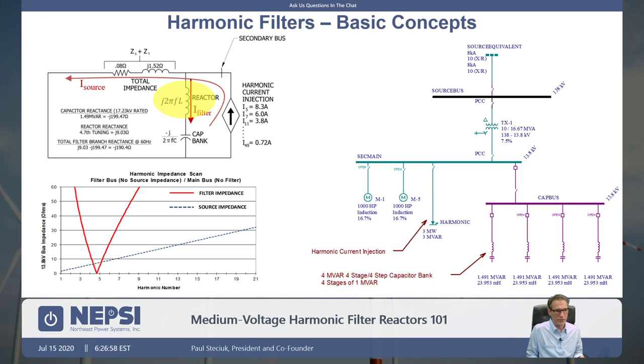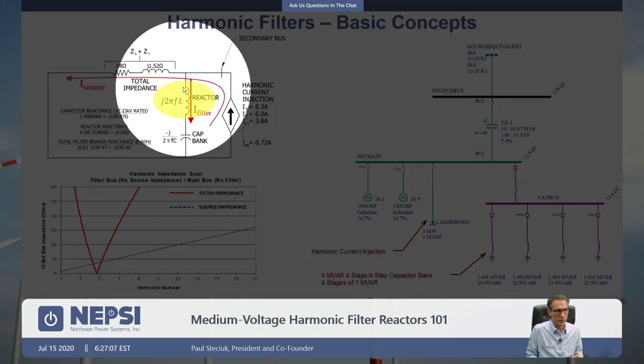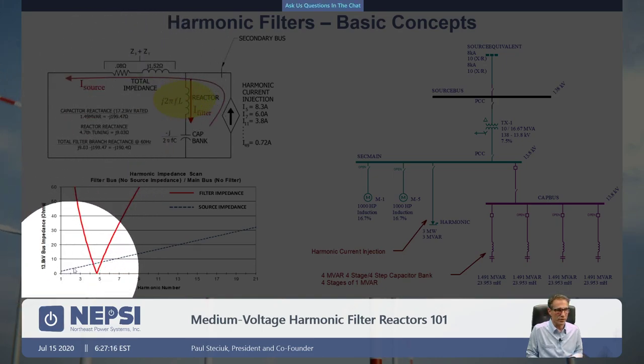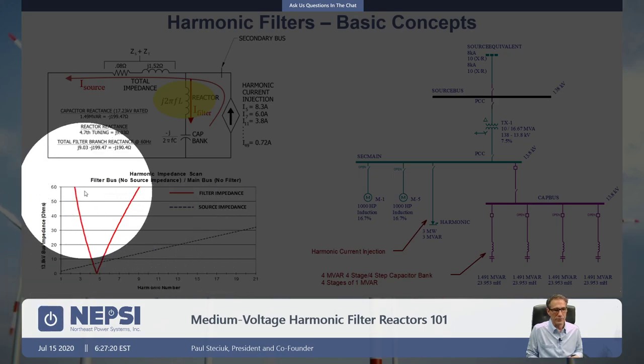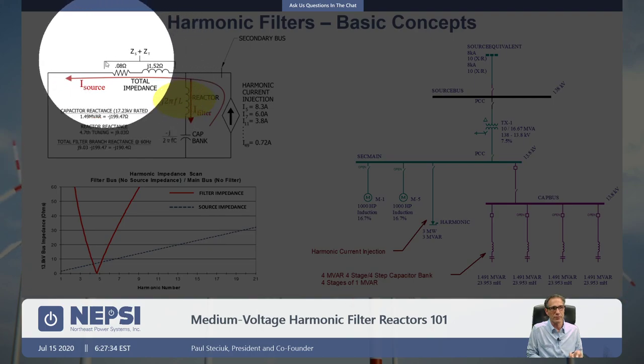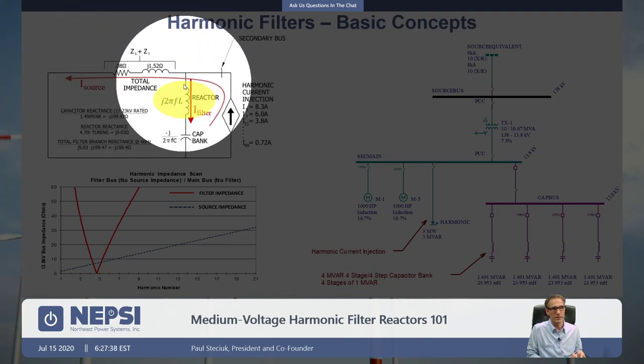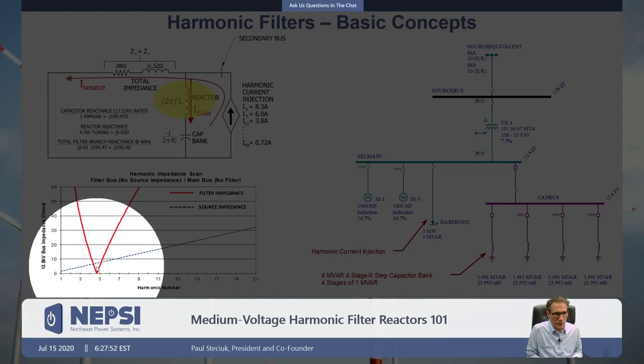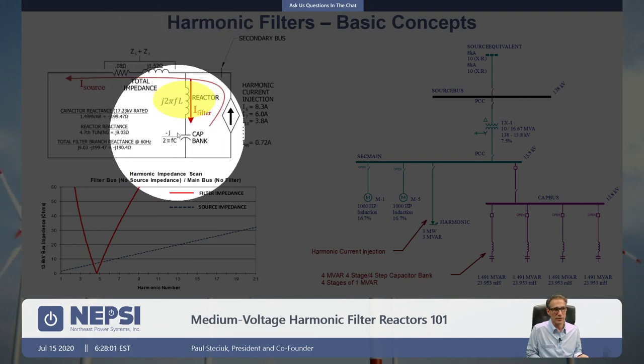Zooming in to the harmonic impedance plot, you see the impedance curve for the harmonic filter. We're looking at the impedance down into the capacitor bank — which includes the reactor and the capacitor — versus the impedance of the source, which is a straight line. When you install a filter on a system, the filter will take harmonic current from the source based upon an impedance current divider between the source/transformer impedance and the filter impedance. At the fifth harmonic, the filter may have an impedance of about five ohms and the source about seven ohms.